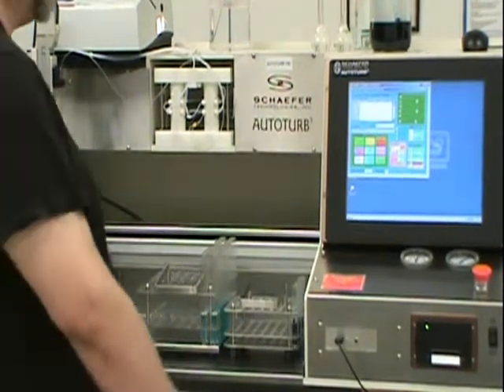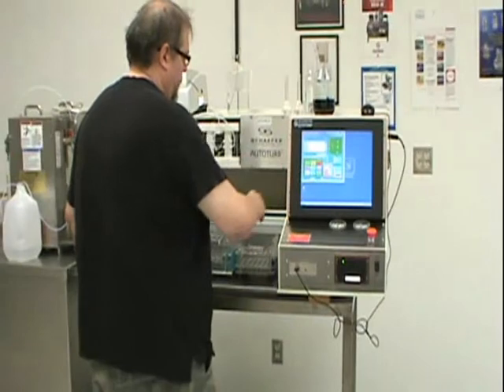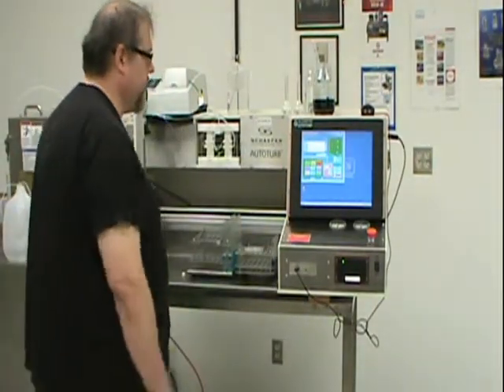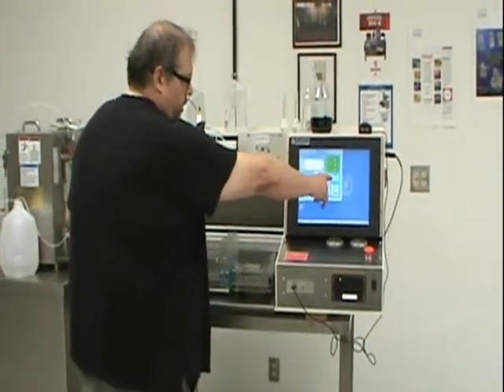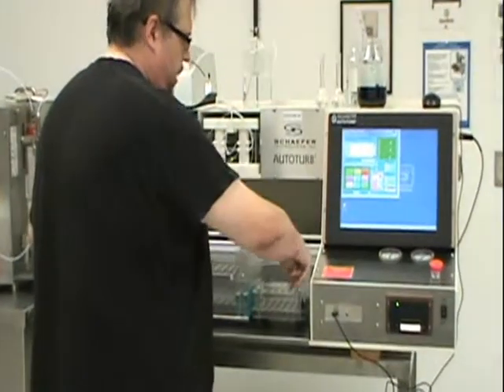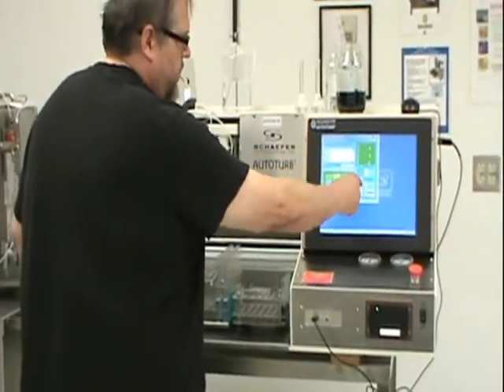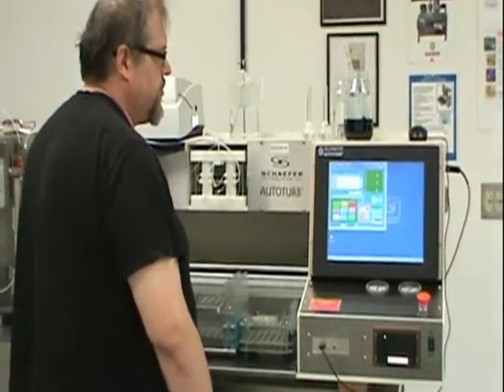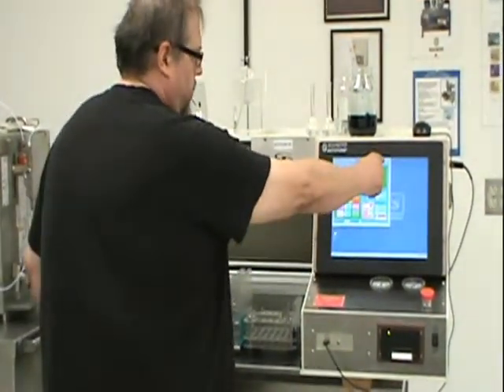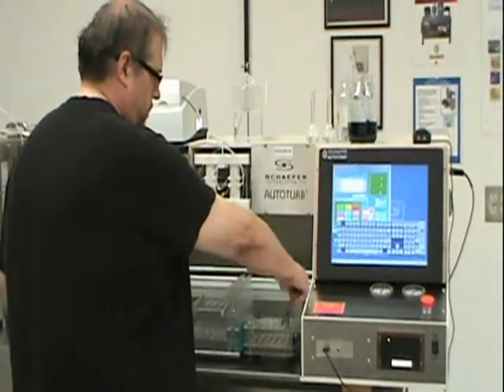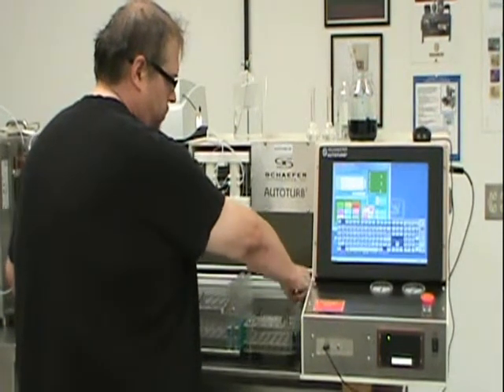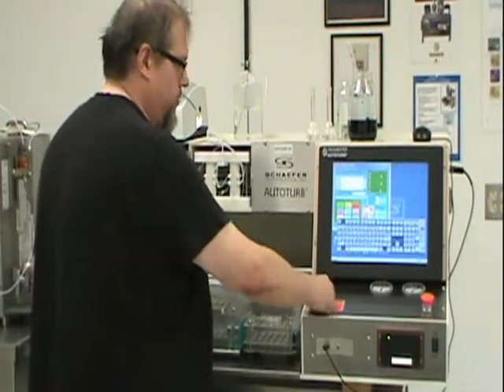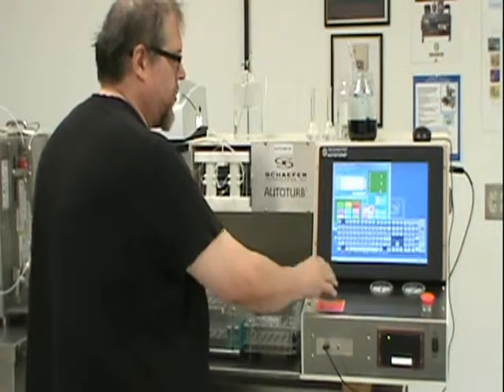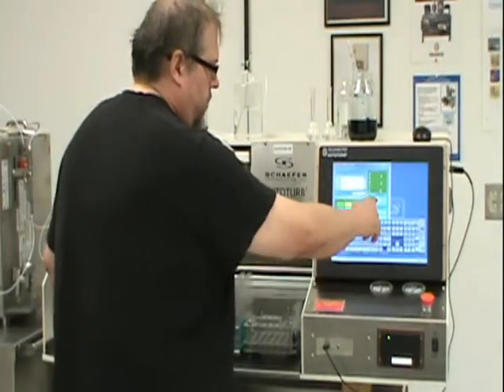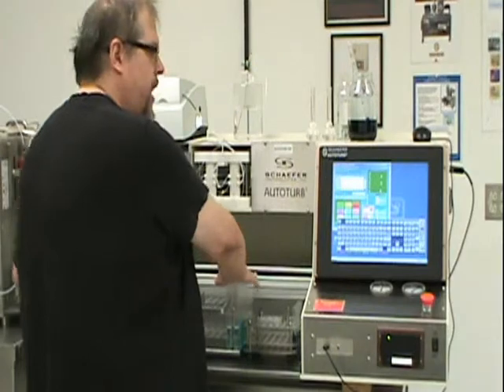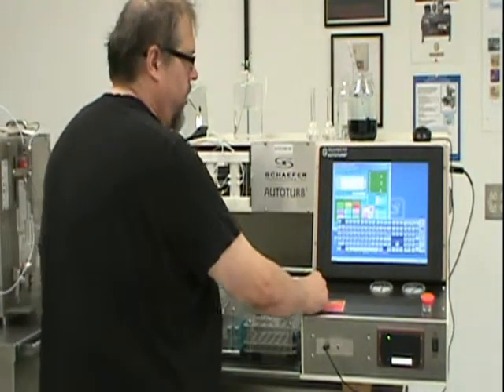The next test we'll do is the diluter normal mode, and we'll continue to fill the same tubes here. We'll tell it that we're going to do 5 samples, 5 tubes in this rack. We're going to tell it in this case that we're going to do 0 flush cycles. A flush cycle would be a buffer or a blank that you would put in here to flush the system out prior to actually diluting samples for the rack. And the flush cycles are not dispensed in the rack. They're dumped in the waste pan and lost.